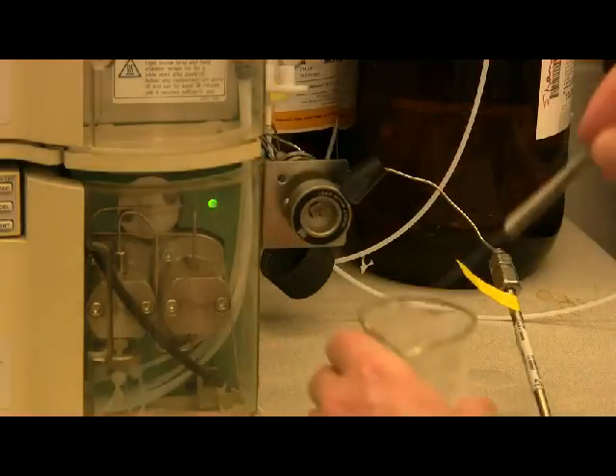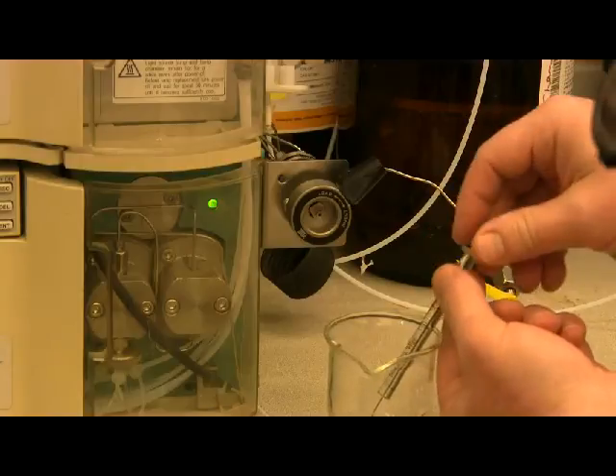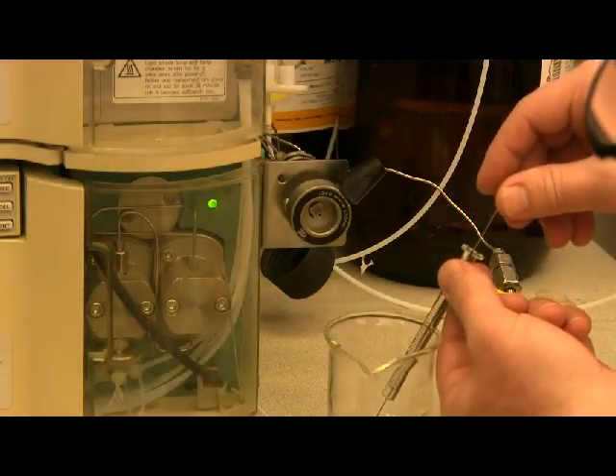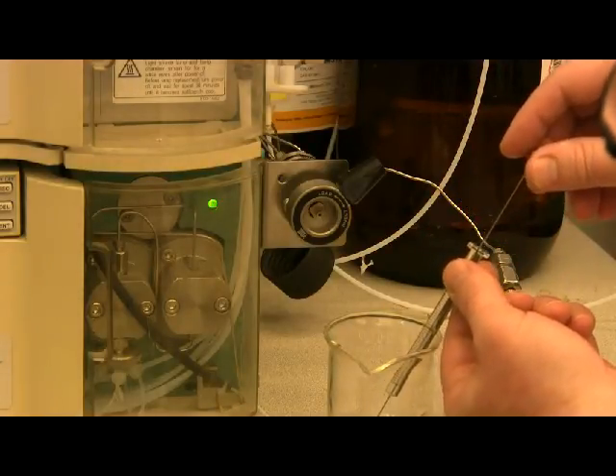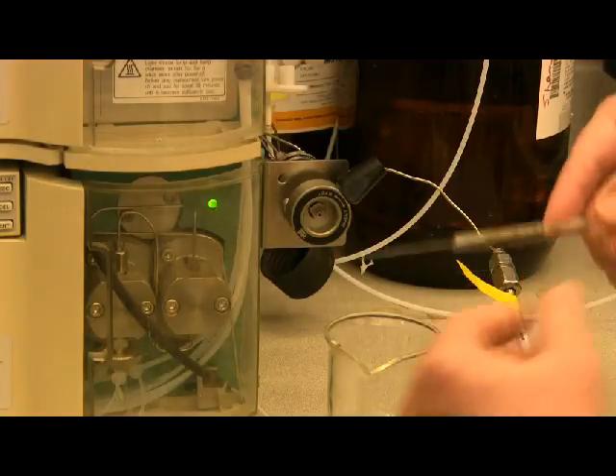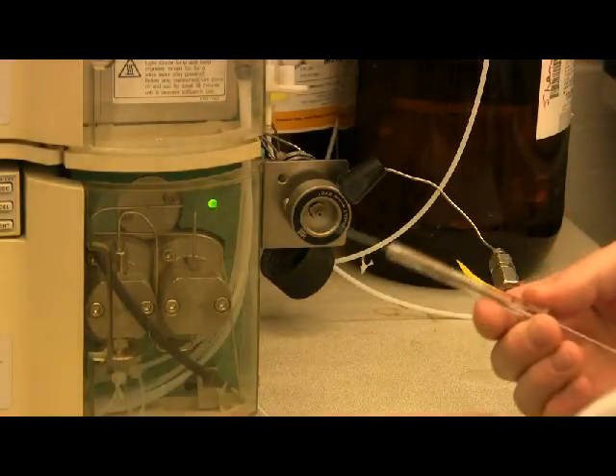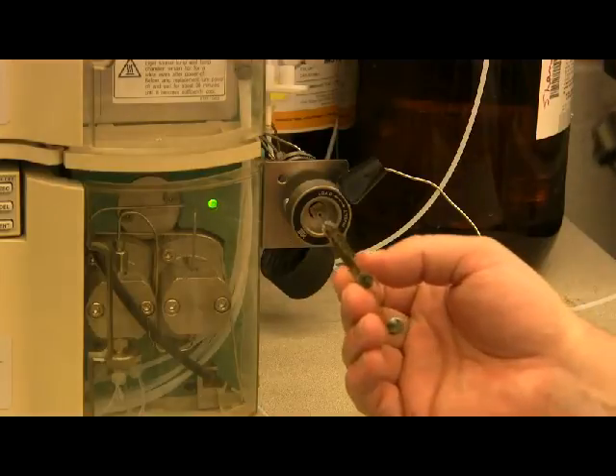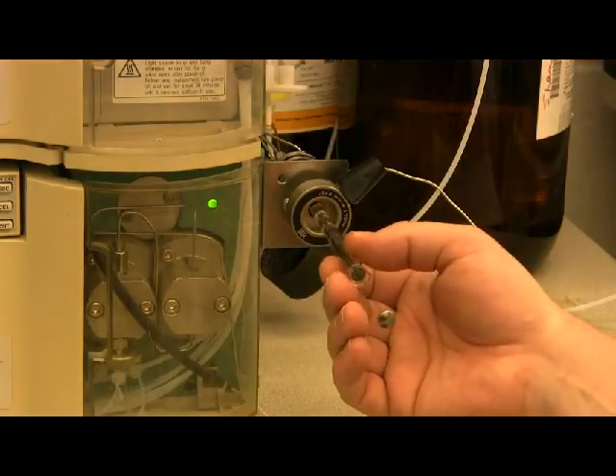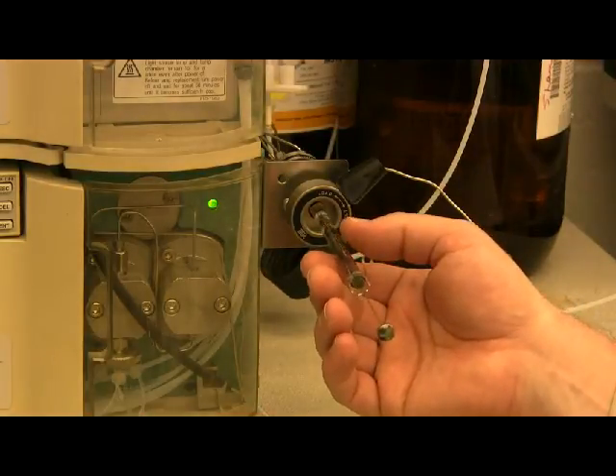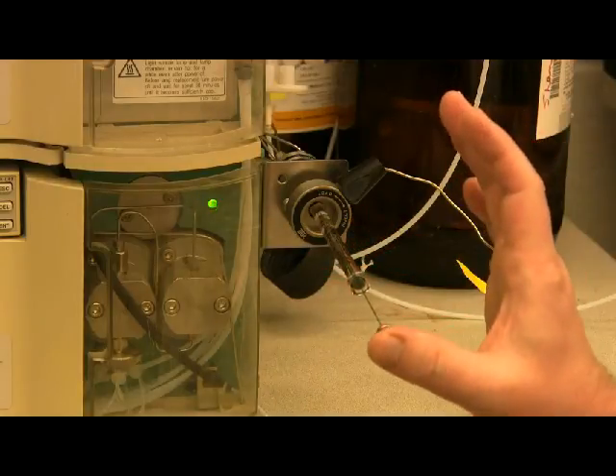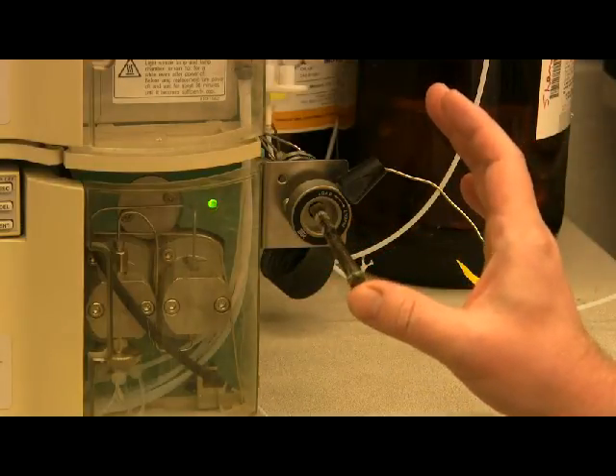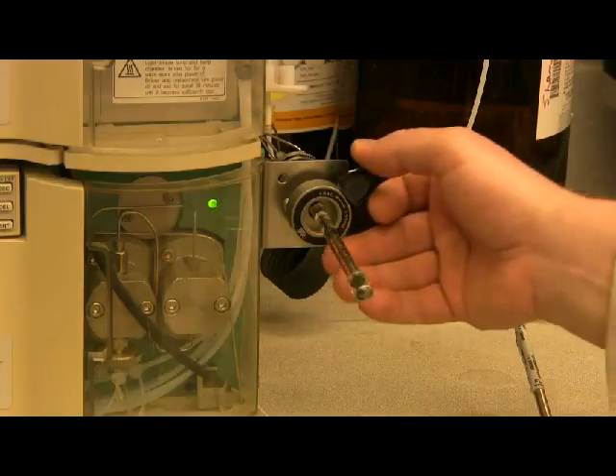So all you do, just draw up your analyte. Here, this is about 50 microliters. Insert it and then push it in, and you can feel that there'll be a slight resistance. Depress the plunger and then turn it down.